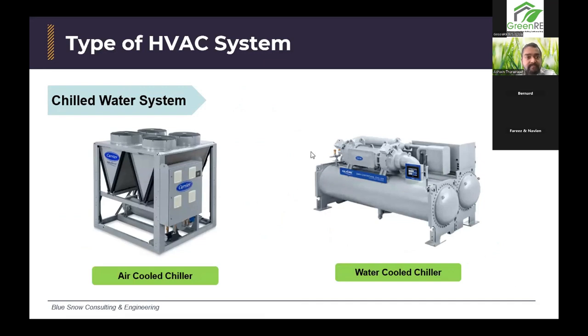In the case of water-cooled systems, it's a chiller that is connected to. It's a central point, one point of contact. Whereas in a refrigerant system, the VRF would be there. So that's why that terminology is often used by typical building management people who say, "Oh, I have a central system." That's what it means. It basically means all your indoor systems are connected to one endpoint, so to speak. Okay, great. So centralized is a more generic term that can apply to package units, water-cooled chillers, etc.